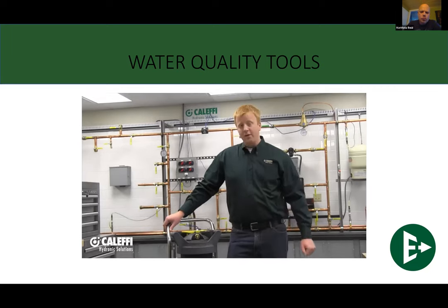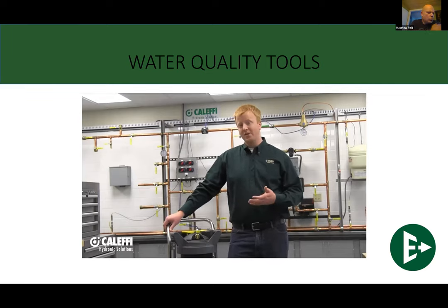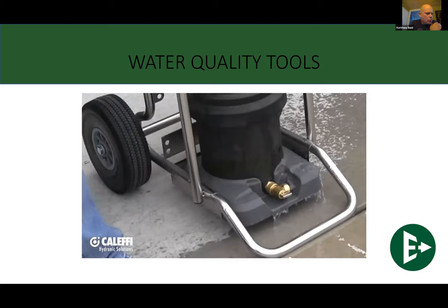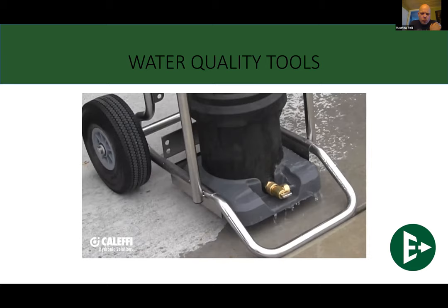Then you're going to want to shut down the drain valve at the very bottom of the Hydrofill unit. At that point, if your Hydrofill is connected to a system that you're filling, you're going to want to isolate that as well. Then you can disconnect all of your hoses from the Hydrofill, then take it over to a floor drain, open up the bottom valve again, and drain all the water from your Hydrofill unit.